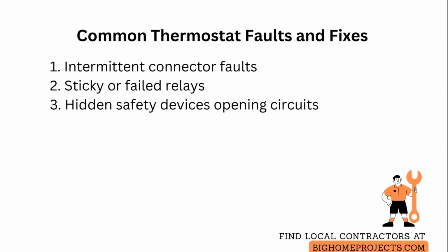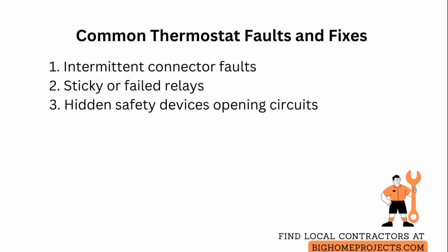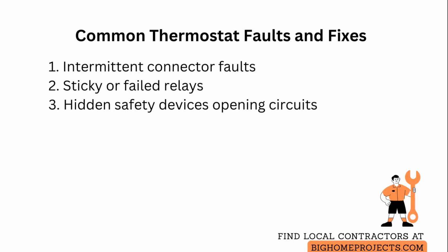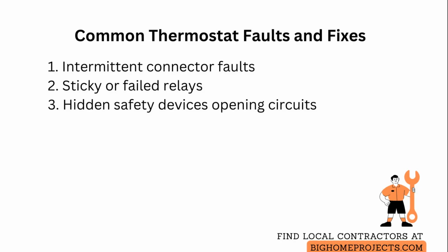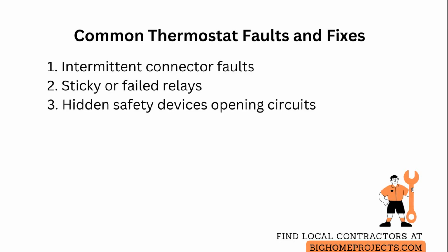For hidden safety devices like overflow switches, door interlocks, or low-pressure cutouts, track down every safety device in the control circuit, bypass temporarily only for testing with a known safe procedure, and then replace the faulty safety device rather than leaving a bypass in place.